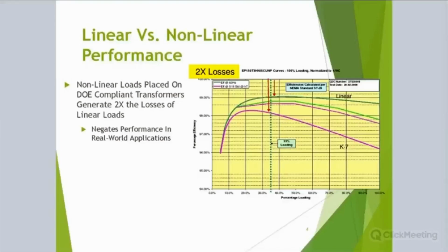A lot of people have a hard time understanding what 1100 watts is, but just take a large hair dryer and figure you're going to turn it on full blast and let it run. That's 24/7, 365. That's what you're losing. So keep in mind, it can add up to quite a bit of energy loss and cost to your facility, especially when you start multiplying these out amongst all your transformers.